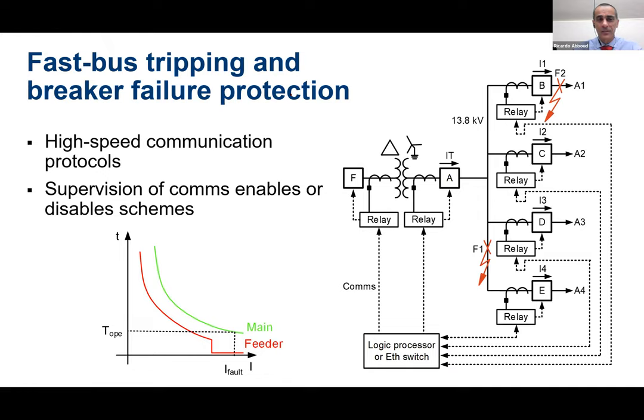So one of them was the fast bus tripping and breaker failure protection. I think you are aware that this is a distribution substation with the transformer, the feeders, the breakers. So this is the main relay, this is the feeder relay. We need to coordinate the overcurrent protection between the main and the feeder relay. So when I have a fault in front of the feeder, only the feeder circuit breaker is supposed to trip. For a fault, I need to have a trip by the feeder and the main relay will not trip. So I need to have this time coordination between the main relay and the feeder relay.